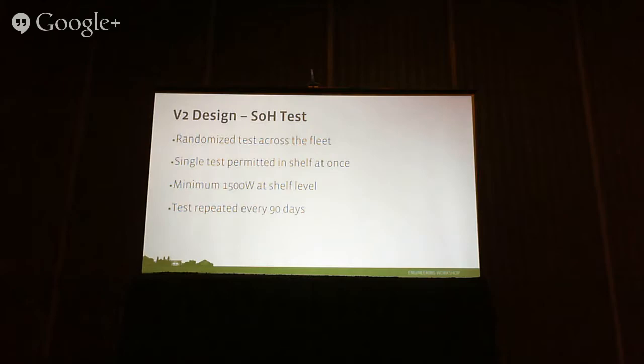To do that, we do state-of-health tests, done randomly across modules. We don't want all the modules to do them at once, because then we might lose redundancy at the time we're doing it. So in one shelf, we only allow one BPU to do it at any given time, and that starts randomly based on a random number implemented inside each module.